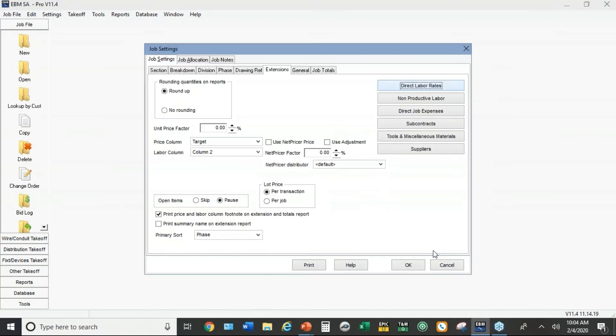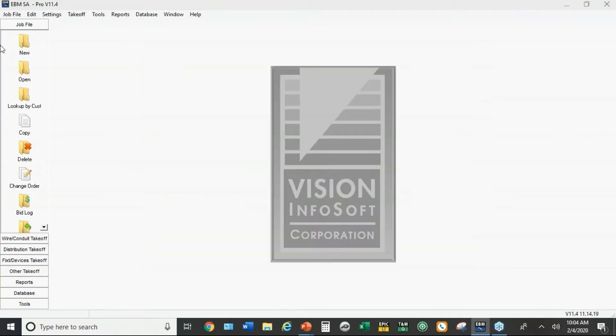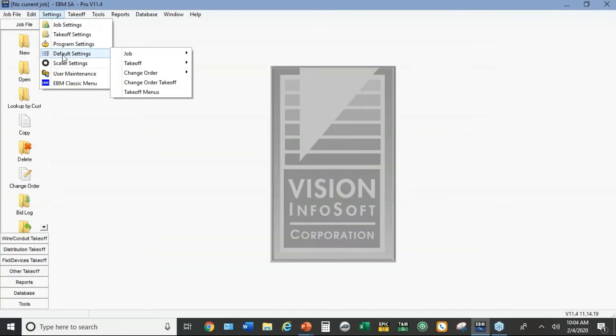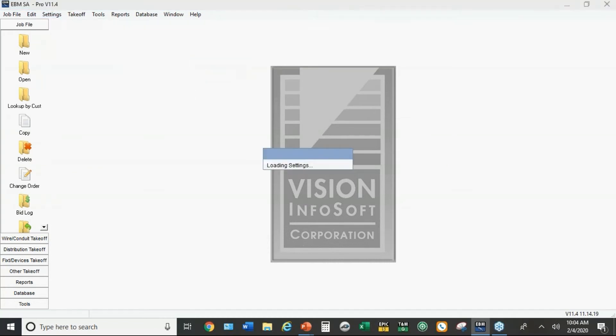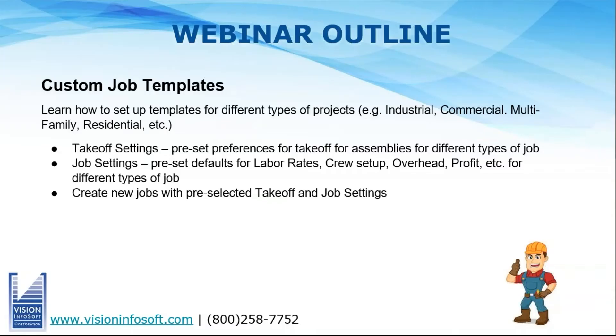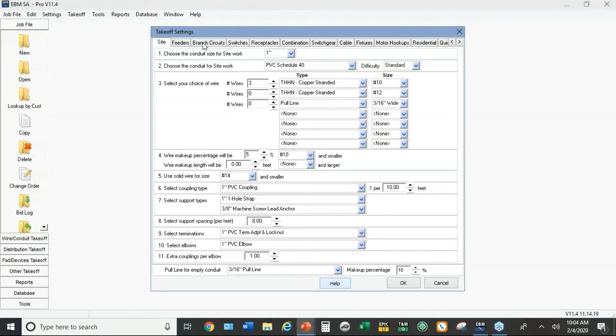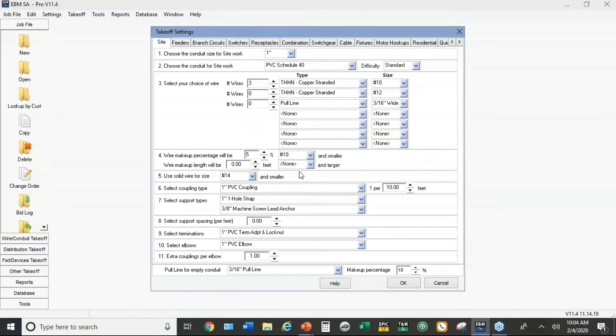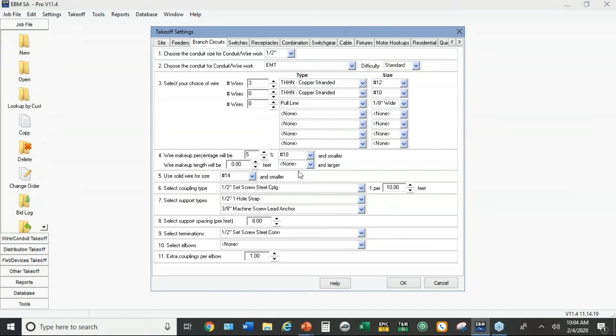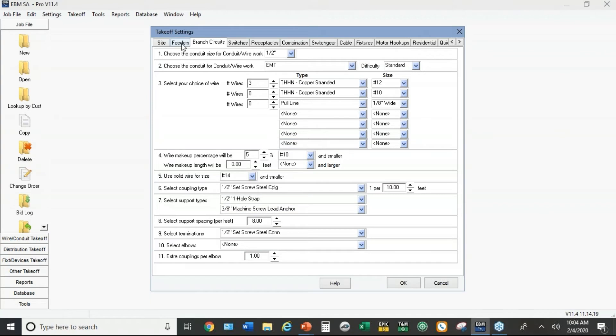The other thing in this setup is a little bit to do with the takeoff, and that's under settings, default settings for takeoff commercial. So every takeoff module in EBM has its own setup. For example, when you open up branch circuits, these are the standard default settings: half inch EMT, number 12 wire, standard set screw steel fittings.